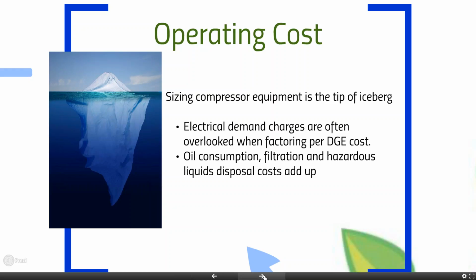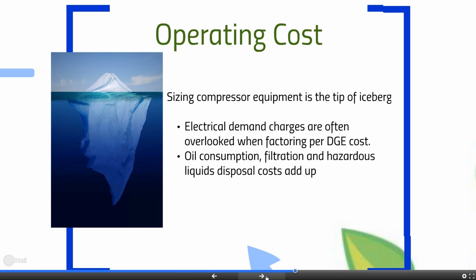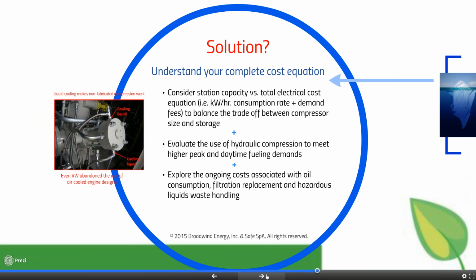And then what do? Now that you've had to manage adding the oil, filtering the oil, now you've got to do something with the oil after you've filtered it off, so you have to deal with that as a hazardous waste. This can add up to a tremendous amount of labor and consumables, such as the filters. And over the course of the lifetime of the station, you're looking at a significant amount of money. A large station could run into $100,000 over 10 years just in oil and filtration costs.